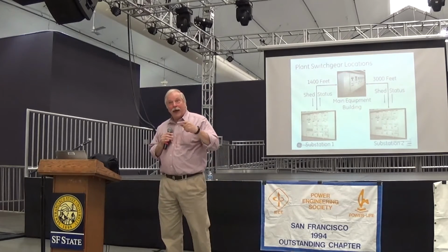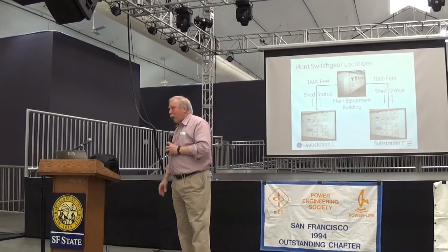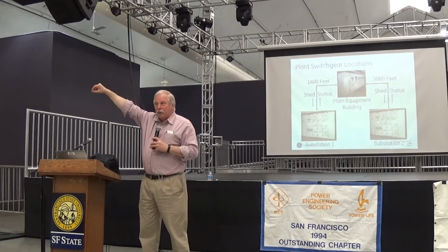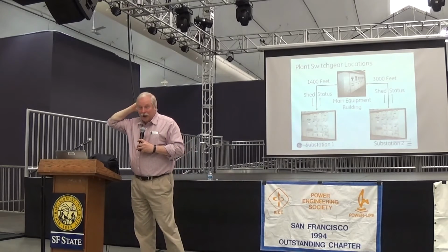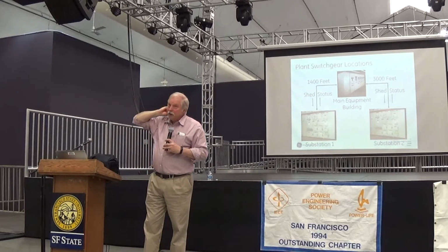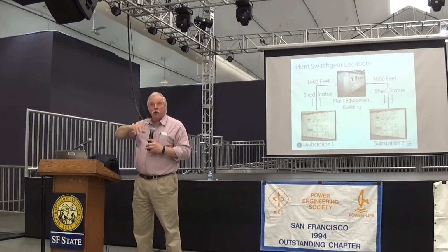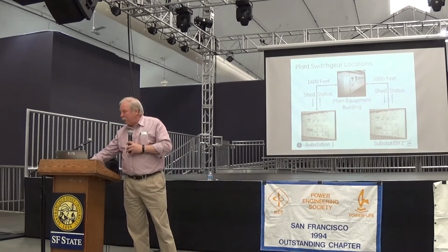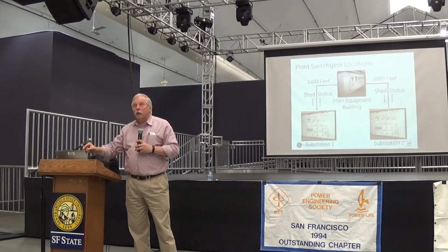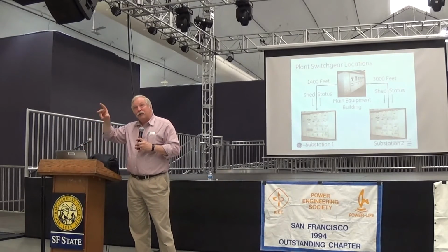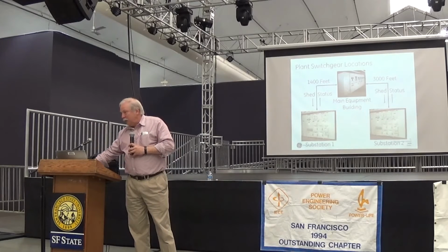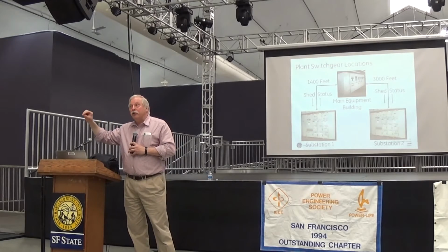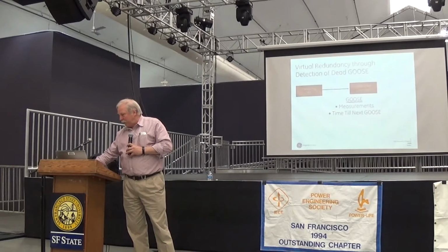And we actually have done one project in Brazil where we went across the Brazilian rainforest with fiber on a remedial action scheme, and that was actually 200 kilometers. Required some special amplification equipment. Anyway, this was set up, and in each of these, there were Ethernet switches that were installed that connected to multiple relays inside these remote substations that were connected to actually trip the loads dynamically.